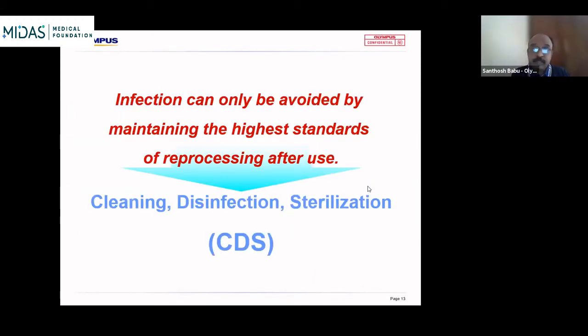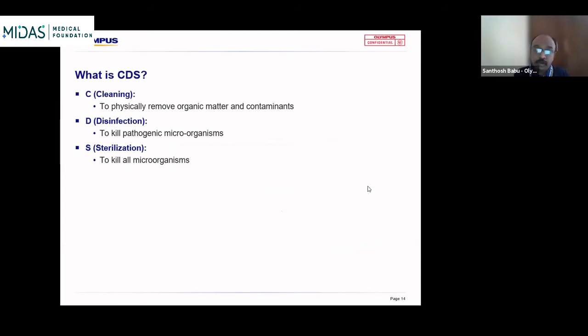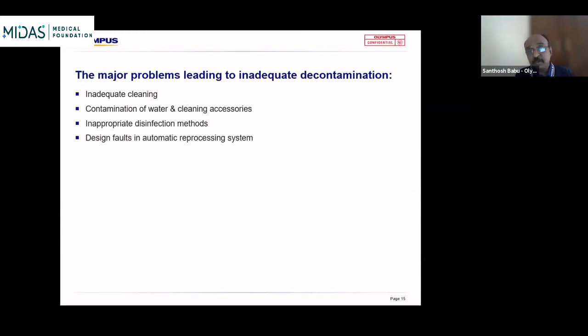Yes, reprocessing has to be done so that you avoid cross-contamination and nosocomial infection, but it can also increase the life of the endoscope. Now, cleaning, disinfection, sterilization, yes. Are these the same? No, all three are different. Cleaning is for removing gross debris, disinfection is to kill pathogenic microorganisms, and sterilization is where you totally kill all the microbial life. Why are we not able to decontaminate the instrument properly? We don't clean the channel or brush the channel. So inadequate cleaning. Water is contaminated. Inappropriate disinfection methods. I've seen people just dipping part of the insertion tube in detergent or disinfectant solution, which is not right. And design faults in the AER also lead to inadequate decontamination.